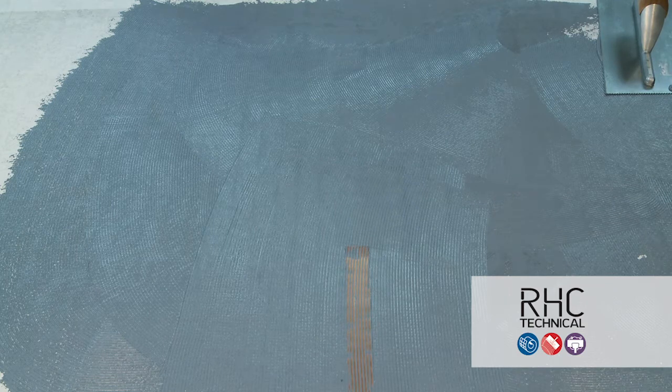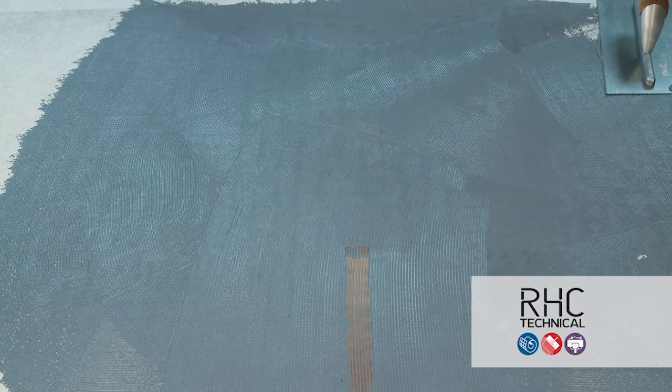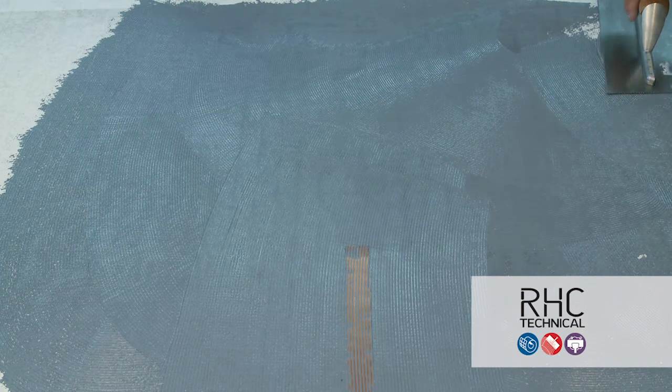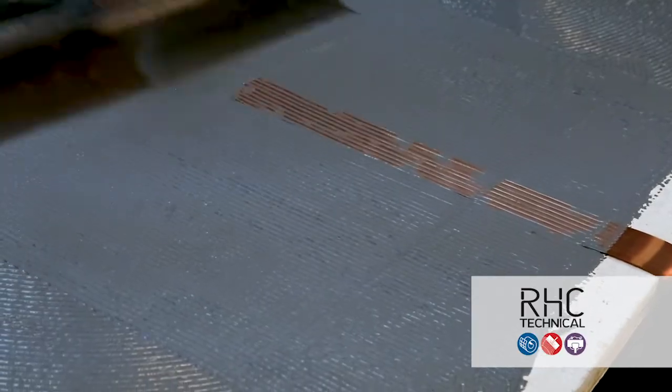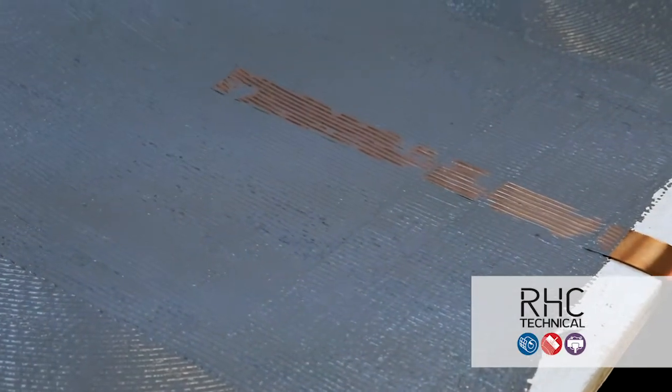Once the initial layer of adhesive is spread, install the copper strap into the adhesive and then apply additional adhesive over the top of the copper strap and make sure it's embedded before installing the tile.